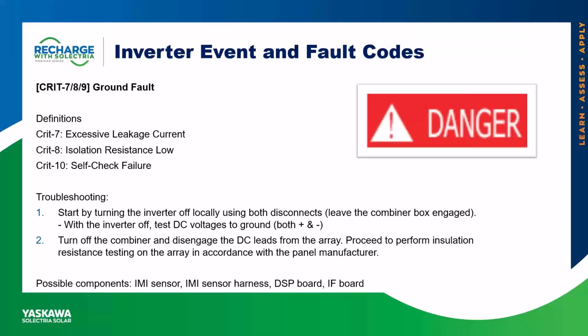After you've verified that voltages bleed, we recommend you turn the combiner off and disengage the DC leads from the array. Proceed to perform insulation resistance testing on the array in accordance with the panel manufacturer. As recommended in the troubleshooting steps, we always want to eliminate the possibility that this is an array side issue.